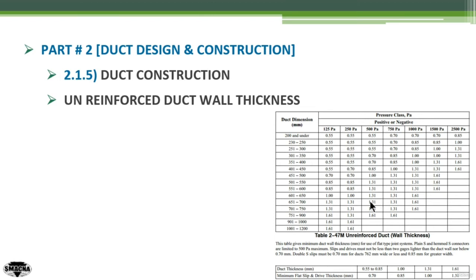The note under this table states that it gives the minimum duct wall thickness in mm. Use of flat joint systems — plain S and hemmed S connectors — is limited to 500 Pascal maximum. Slip and drives must not be less than two gauges higher than the duct wall, and not below 0.7 mm. Double S slip must be 0.7 mm for ducts 762 mm wide or less, and 0.85 mm for greater widths.